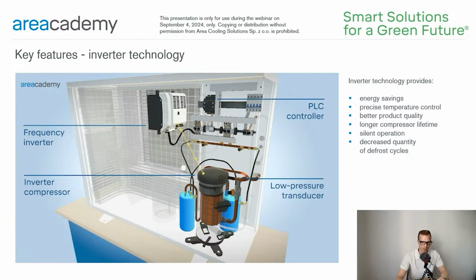The inverter technology system consists of 4 main components: the low pressure transducer, the PLC controller, the frequency inverter, and the inverter compressor. The cooperation of these 4 main components is presented in the visualization. The low pressure transducer sends a signal about the current suction pressure to the controller. And then the controller is connected to the inverter and provides information if the compressor should speed up or slow down.